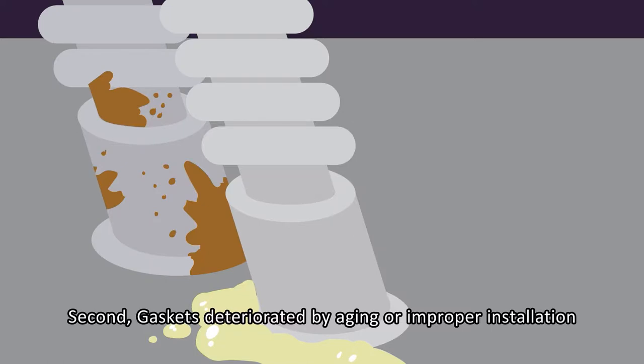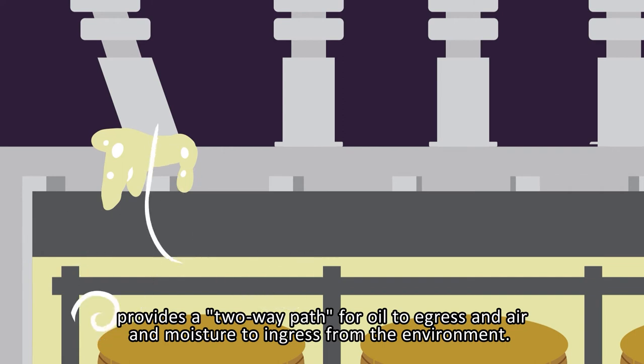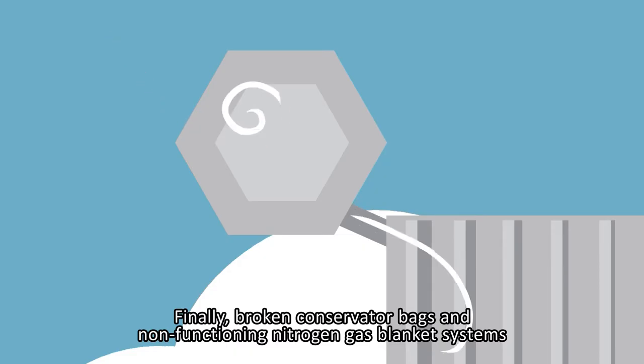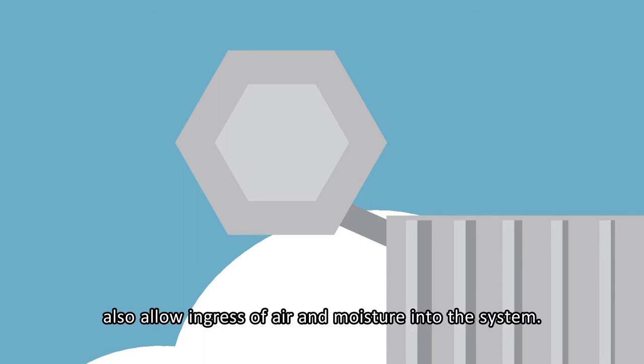Second, gaskets deteriorated by aging or improper installation provide a two-way path for oil to egress and air and moisture to ingress from the environment. Finally, broken conservator bags and non-functioning nitrogen gas blanket systems also allow ingress of air and moisture into the system.